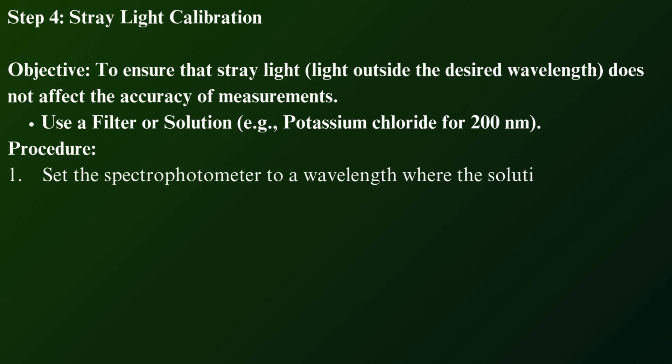Step 4: Stray light calibration. Objective: To ensure that stray light—light outside the desired wavelength—does not affect the accuracy of measurements. Use a filter or solution, for example, potassium chloride for 200 nanometers. Procedure: Set the spectrophotometer to a wavelength where the solution or filter is supposed to absorb all light, e.g., potassium chloride at 200 nanometers.